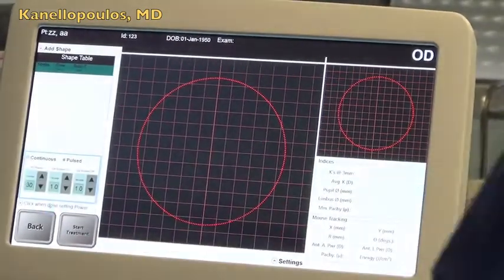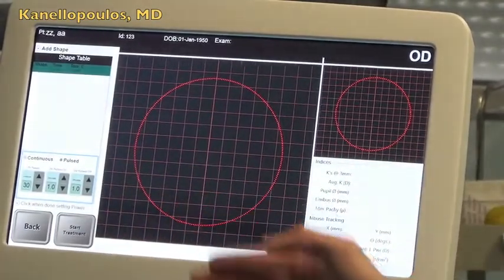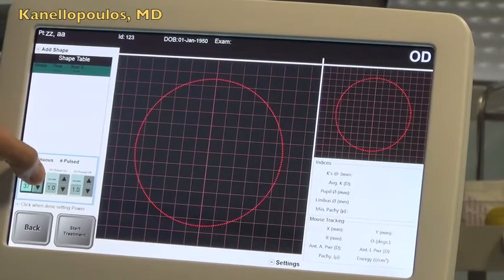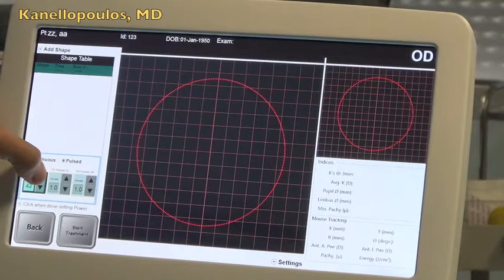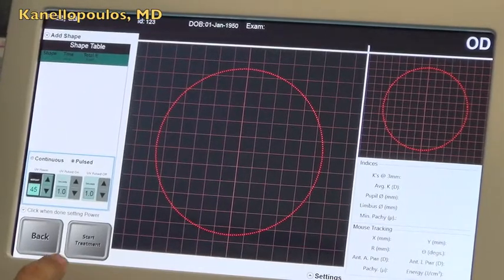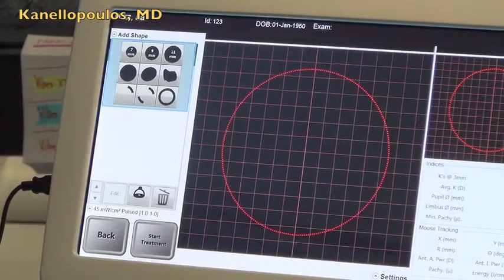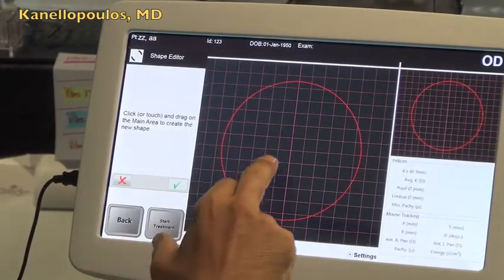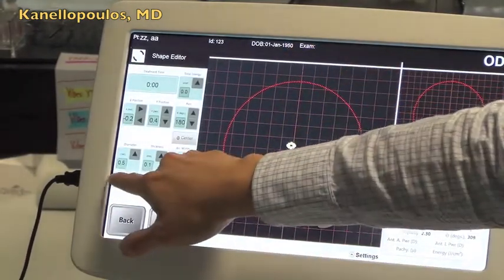Here you have the option of choosing power levels, continuous or pulsed, and also varying the amount of time that the UV is on and off. Let's go with 45 milliwatts, which would be the power threshold we want to use for dramatic shape changes in the cornea. Then we click and add a shape — we can bring in a circle, for instance, and try to expand that.